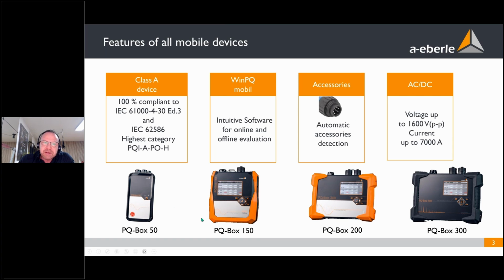All our analyzers are 100% compliant to the important standard 61000-4-30, and all our analyzers comply to Class A devices. And inside this standard, there are different other standards directly linked, and for the interference of our devices, we are also here in the highest category for harsh environment. So the devices can withstand the highest transient and EMC fields.